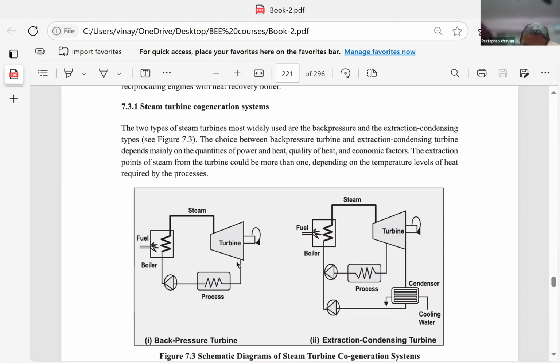Instead of throwing away the output of the turbine, instead of the steam going to a condenser and letting out the waste heat to the cooling water, we do not allow the steam to go down to negative pressures or vacuum pressures. No, we will stop it here. We will not extract the full heat of the steam for conversion into electricity. Partial pressure and temperature steam will be given to a heating process into the industry. This process means an industrial process for which heat is required. So instead of going to the condenser, it will go to the industry.